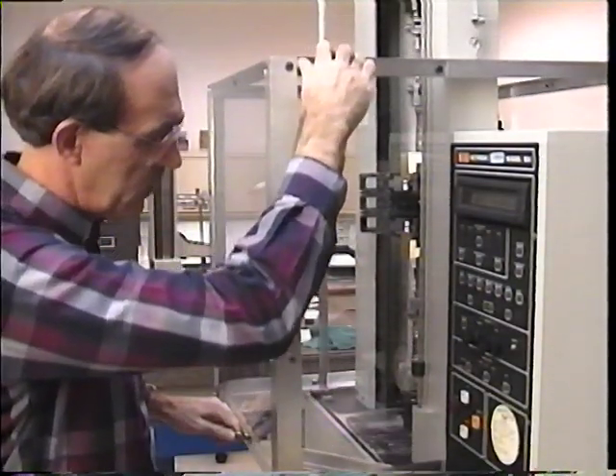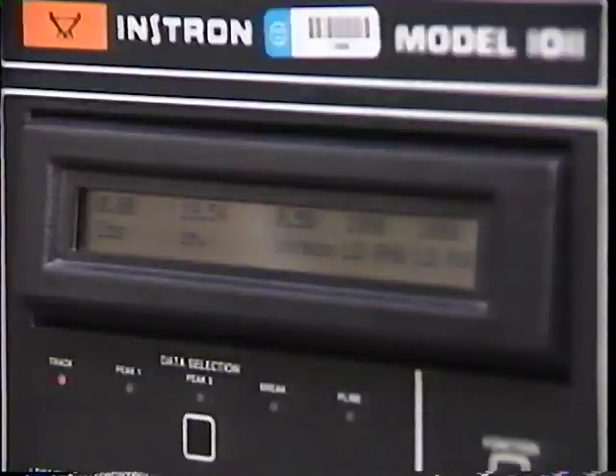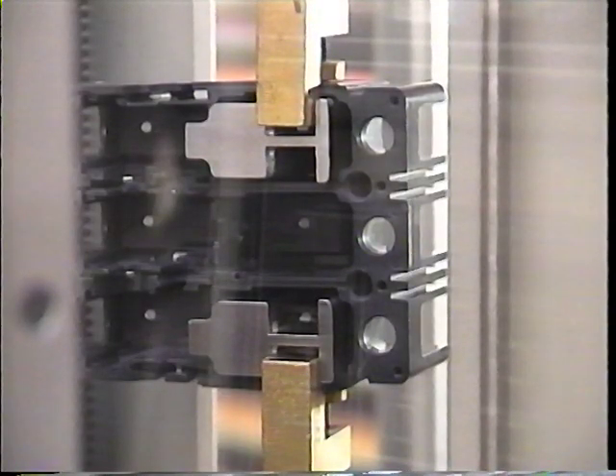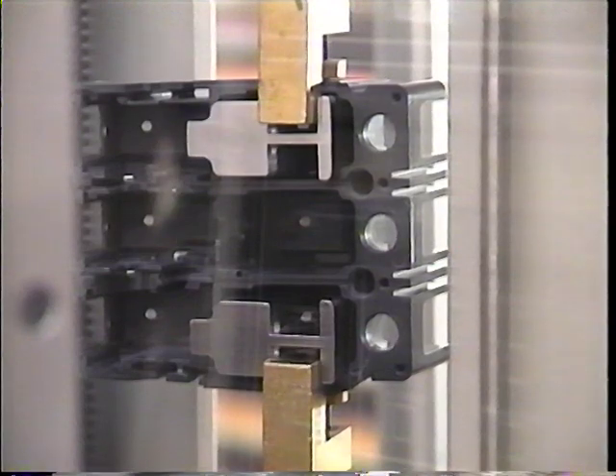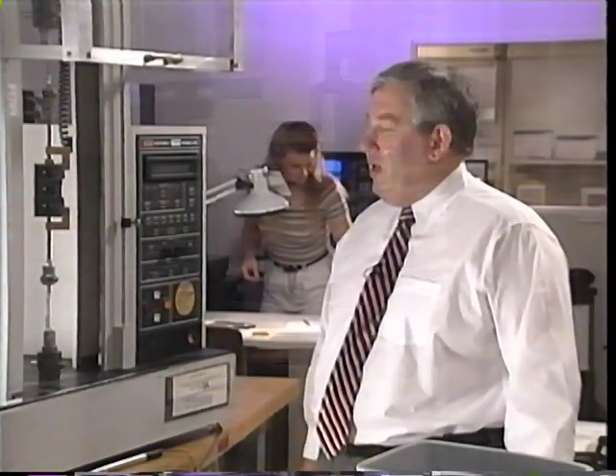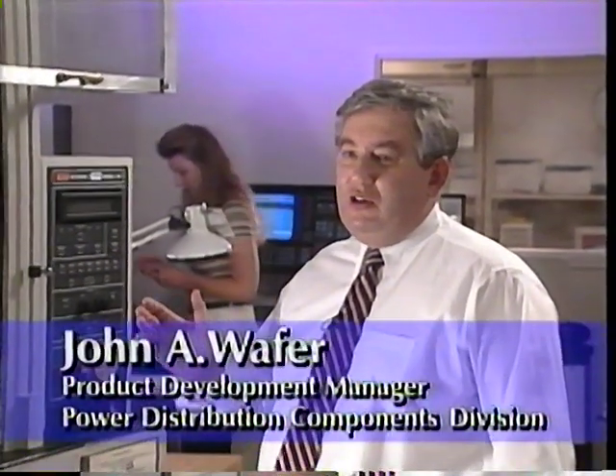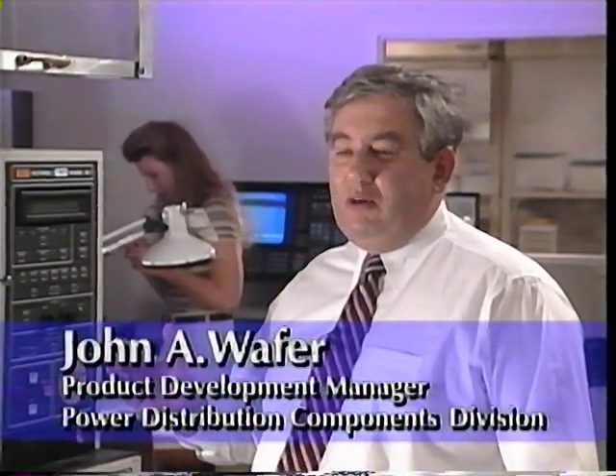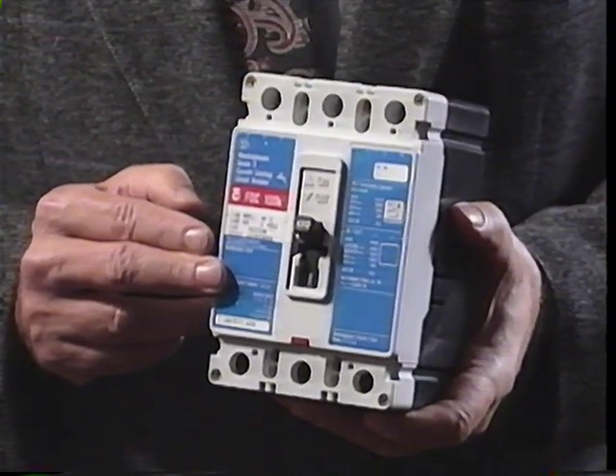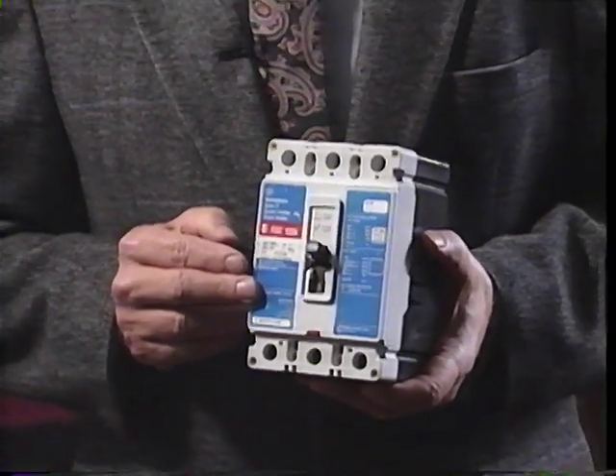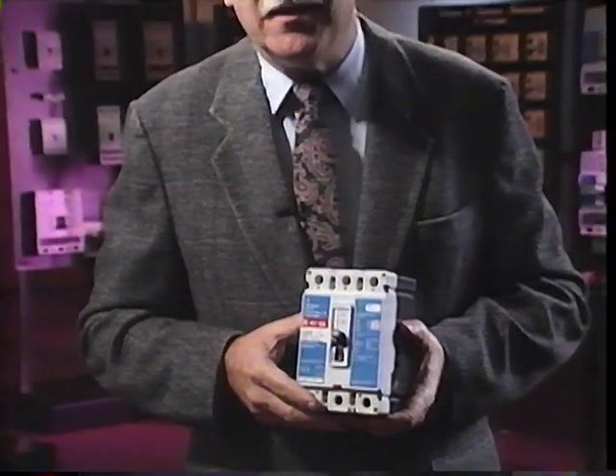Arc physics forms the center of the work here, but the physics, engineering, and chemistry of the materials that form these electrical circuit protective devices are a discipline in their own right. The materials we use to make a circuit breaker have to be strong and resilient because of the internal pressures that are generated when a circuit breaker interrupts a major fault current. The pressure inside a breaker case under fault conditions may exceed 100 psi. What materials can hold such strain and still be affordable? The search for the next material or process goes on here, always seeking the slightly better result, never quite satisfied.